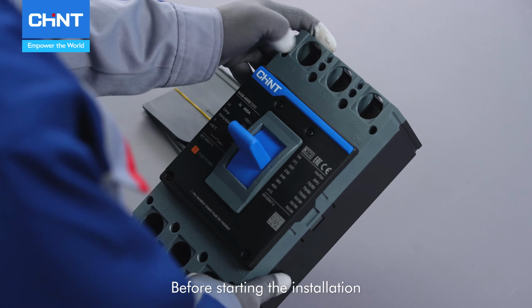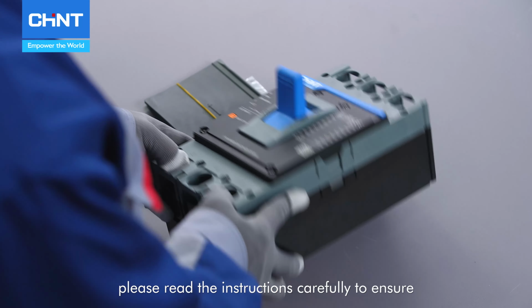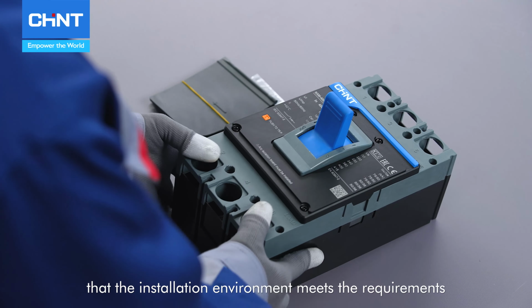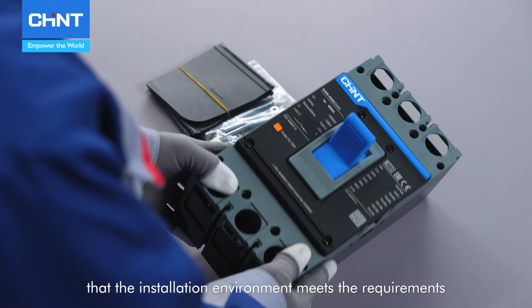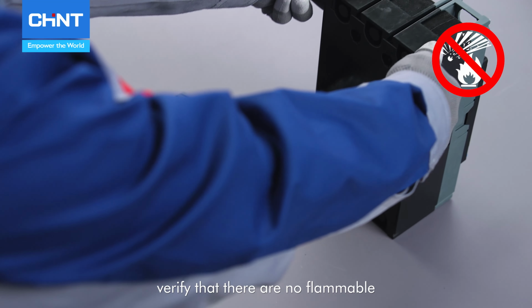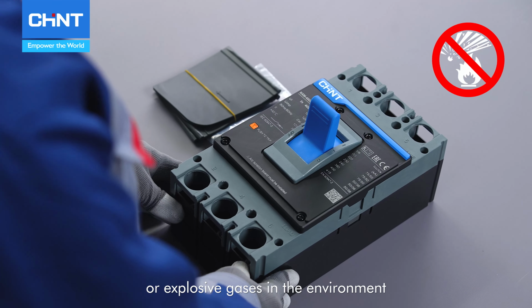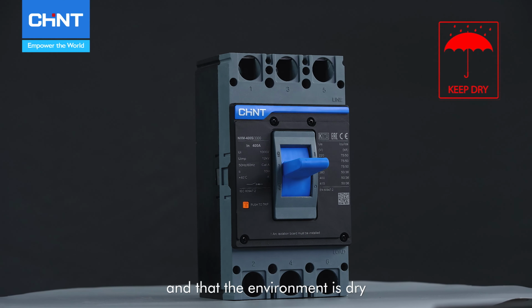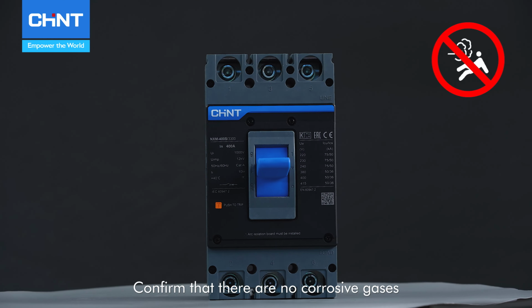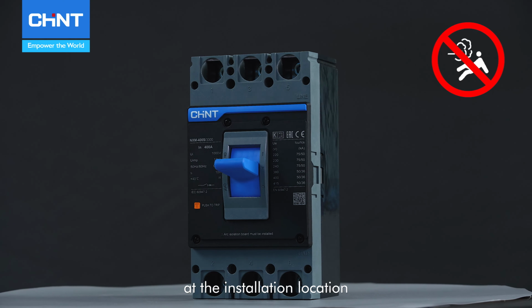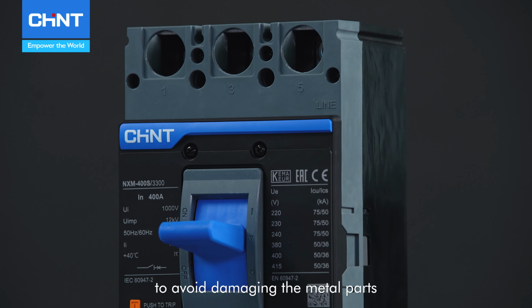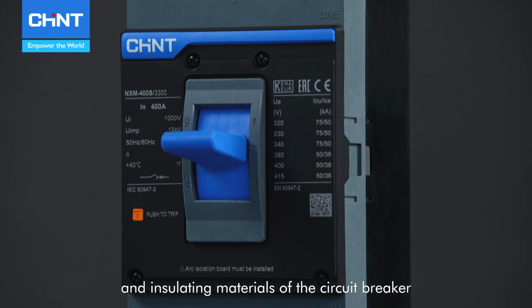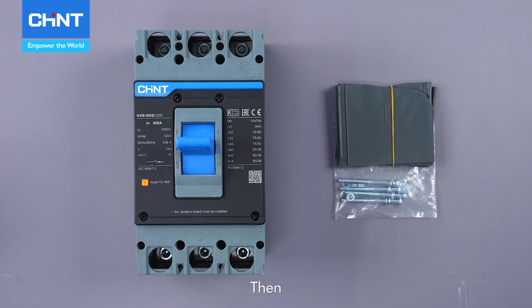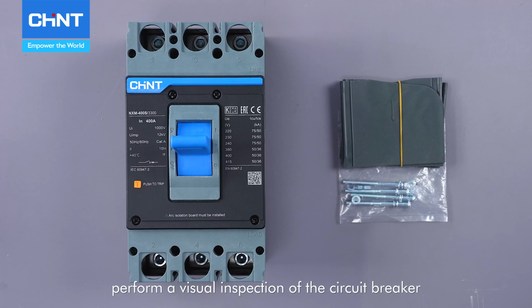Before starting the installation, please read the instructions carefully to ensure that the installation environment meets the requirements. Verify that there are no flammable or explosive gases in the environment, and that the environment is dry. Confirm that there are no corrosive gases at the installation location to avoid damaging the metal parts and insulating materials of the circuit breaker. Then, perform a visual inspection of the circuit breaker.